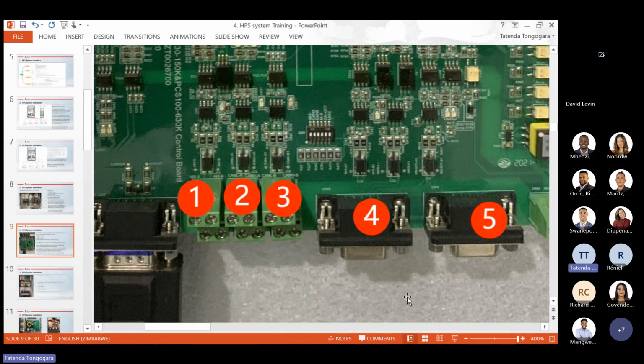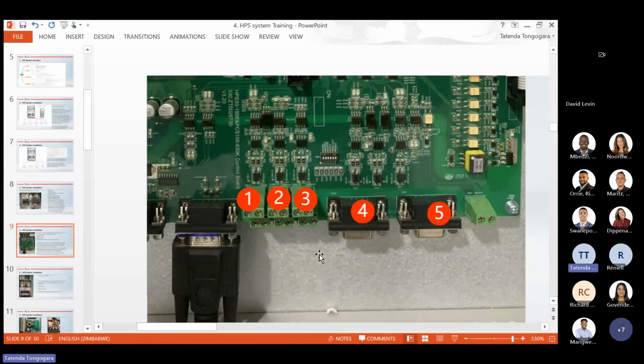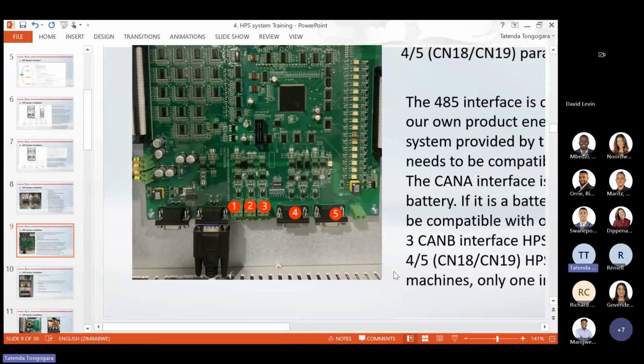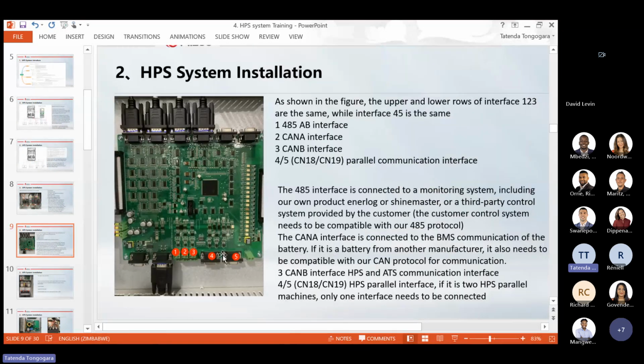And then number 4 and 5 are used when you are running a parallel system. You just daisy chain your inverters. So if you connect master on number 4, on the slave you connect 5, and then if you have 4 inverters, you just daisy chain them.